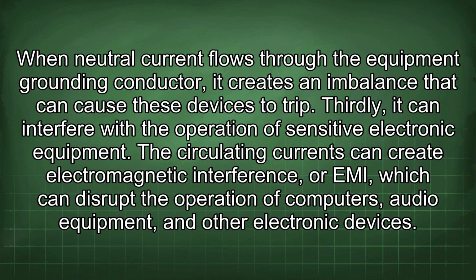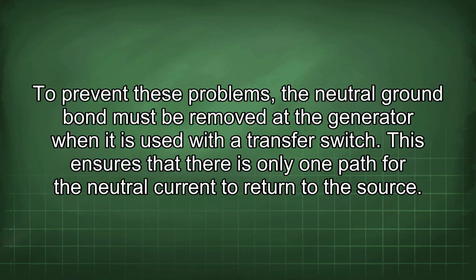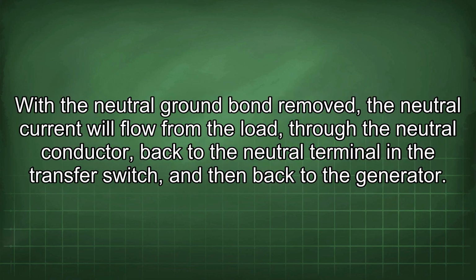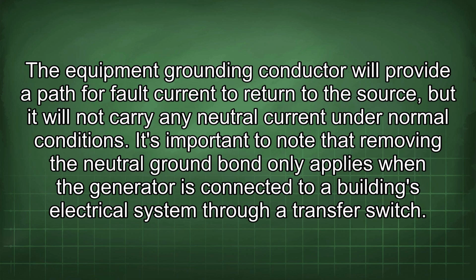To prevent these problems, the neutral ground bond must be removed at the generator when it is used with a transfer switch. This ensures that there is only one path for the neutral current to return to the source. With the neutral ground bond removed, the neutral current will flow from the load, through the neutral conductor, back to the neutral terminal in the transfer switch, and then back to the generator. The equipment grounding conductor will provide a path for fault current to return to the source, but it will not carry any neutral current under normal conditions.